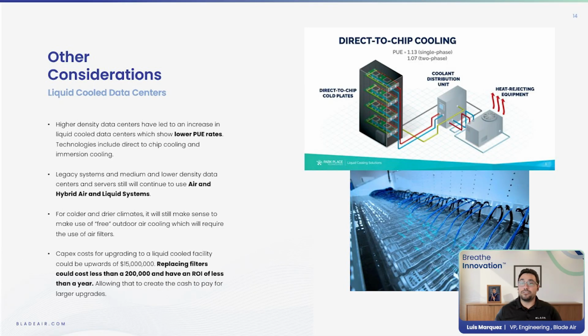Finally, I would not like to miss addressing liquid cooled data centers. The reality is higher density and need for lower PUE rates means that more liquid cooled data centers have and will enter the market. The reality is liquid fluids have better heat transfer than air, and so will naturally lead to better heat exchange and lower PUE. There are two main types of liquid cooled data centers. There's the direct to chip cooling that brings the fluid to the chips. And then there's also immersion cooling where the entire rack is submerged in a non-conductive fluid.